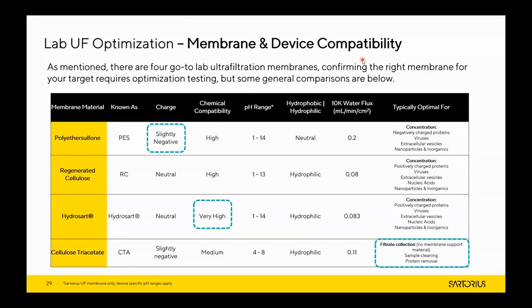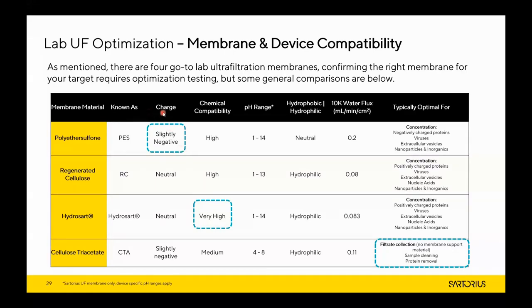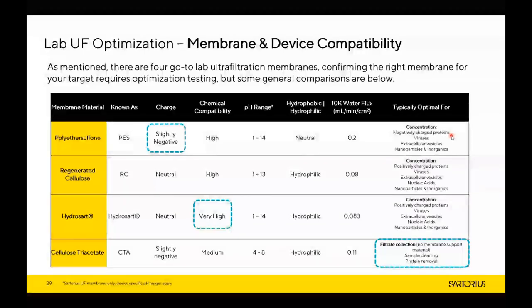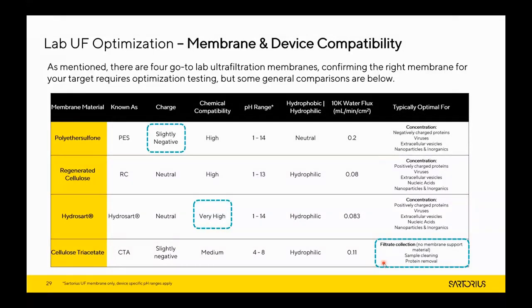When choosing the membrane, Sartorius is in a good position with four go-to lab ultrafiltration membranes, ensuring the right membrane for each application. Polyethersulfone has a slight negative charge at neutral pH, making it optimal for retaining negatively charged proteins. Hydrosart has the highest chemical compatibility, making it very good for inorganic work. Cellulose triacetate lacks the membrane support material, making it very good for filtrate collection, sample cleaning, and protein removal.